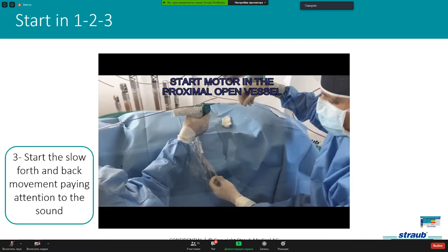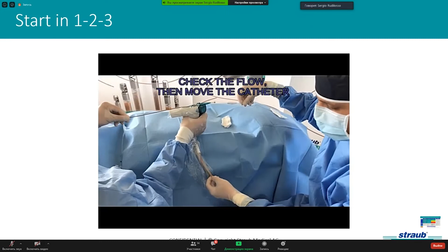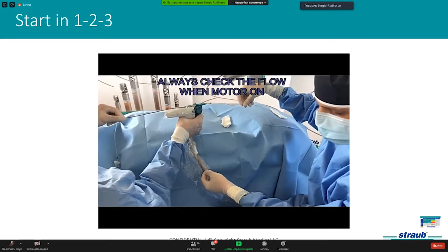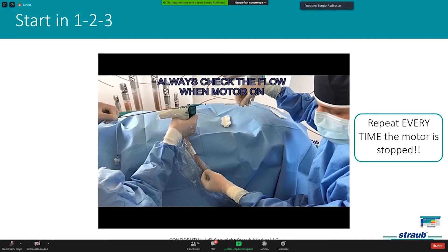As you see here in the video of the perfect second operator, we start the catheter without touching it. Then we check the flow, and then we start movement. 1, 2, 3: motor, flow, movement. And we have to repeat it every time the motor is stopped. Go back to the open proximal vessel, then start the motor, check the flow, and move the catheter.